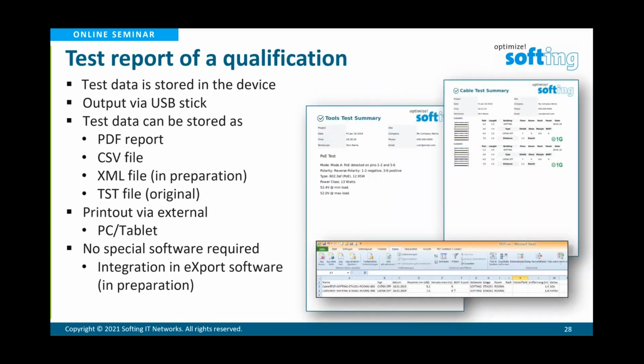The test reports of a qualification more or less cover the wiring, the delay skew, the SNR, and the capability of the transmission. You can store this in the devices—there's a lot of storage space for several thousand test results. Tests can be stored as a direct PDF report, a CSV file, an XML file that's in preparation, and the original TST test files.